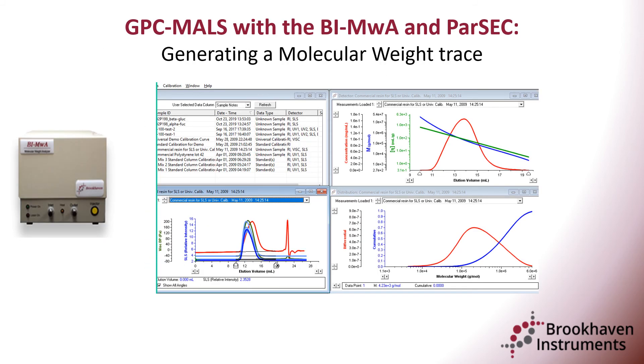The MWA can acquire the analog output from a variety of detectors that may already be part of an existing GPC system, to provide additional detection capabilities such as viscosity, UV, and RI. This data can be read into the Brookhaven Instruments size exclusion chromatography acquisition software, PARSEC, to produce a unified chromatogram.